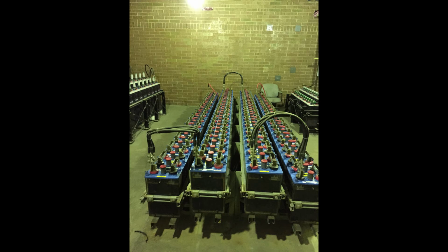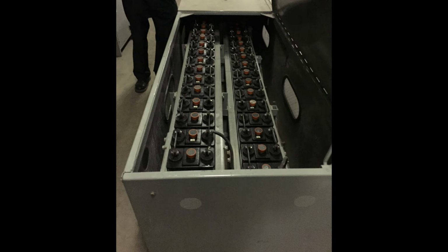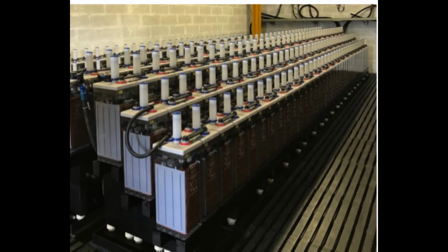What you do now to remove that path is dependent upon the cell type. If this is a vented, flooded, wet cell, whatever you want to call it, and let's say you still cannot see anything, you need to neutralize all surfaces of the jar plus the battery rack, rail covers, and rails as best you can. If this is a VRLA string with individual cells or units that are sitting on a standard open type battery rack with rails, in other words, the same type of racks as for the vented cells, then the neutralization process is the same as for the vented cells.